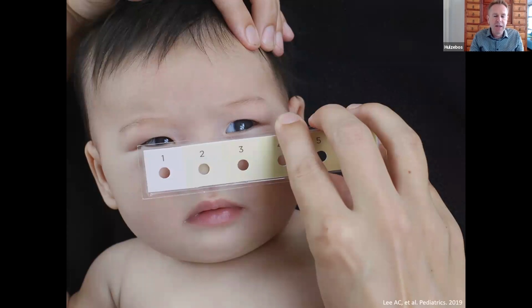In the USA and Bangladesh, a completely renewed icterometer, the Bili-ruler, was tested in about 800 neonates younger than 28 days to identify jaundice. As you can see here, the Bili-ruler has 6 color strips that were developed by processing digital color photographs of newborn infants with different levels of serum bilirubin.